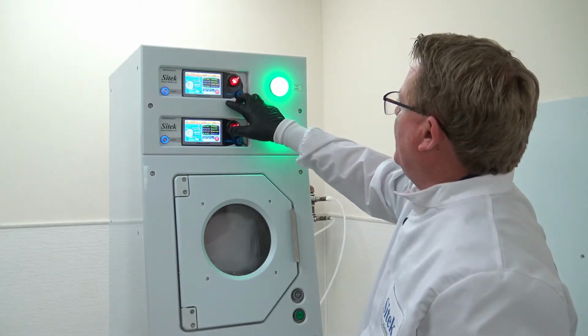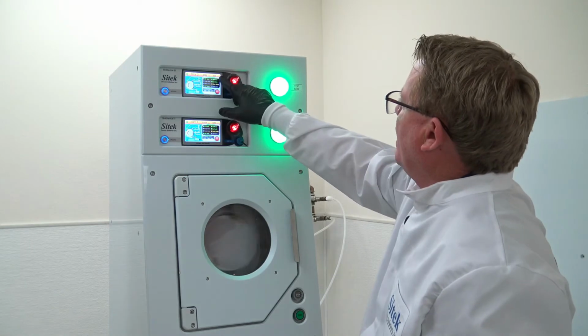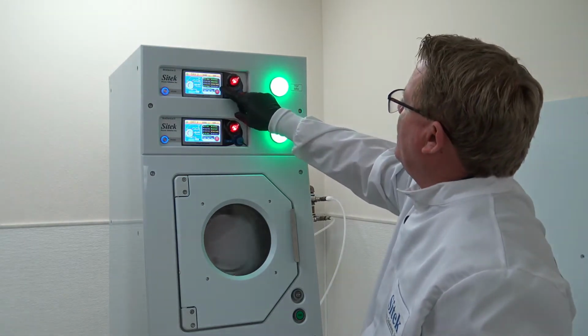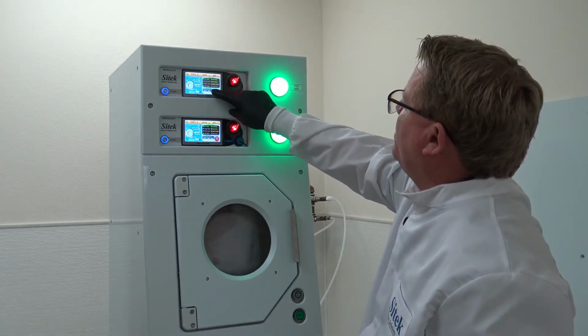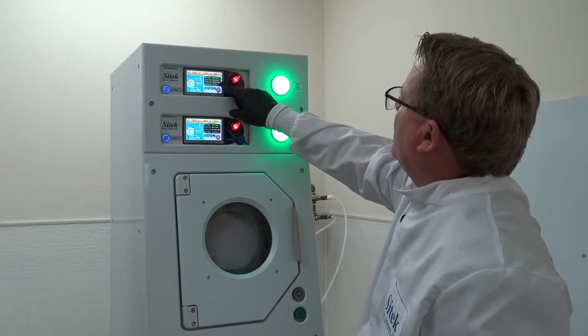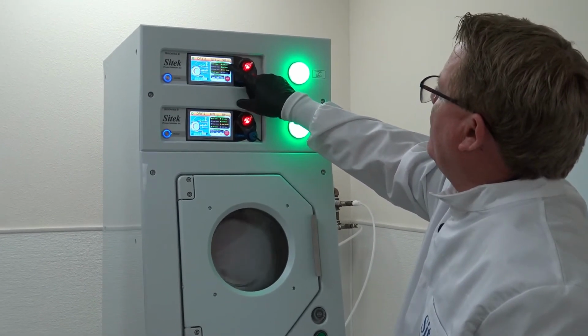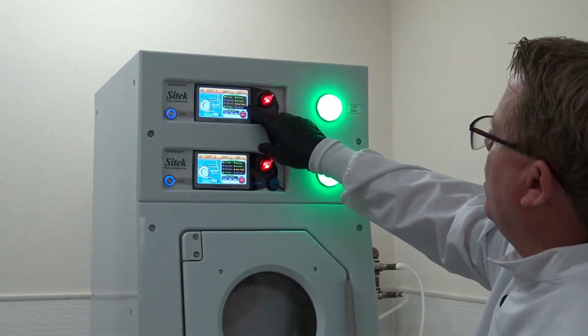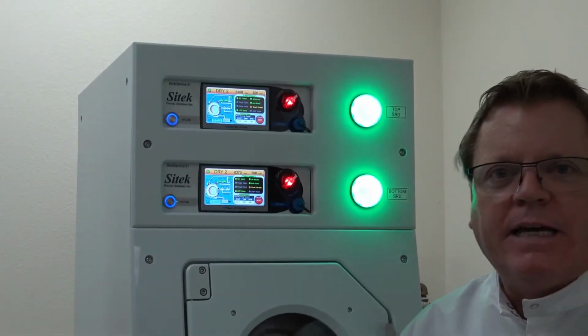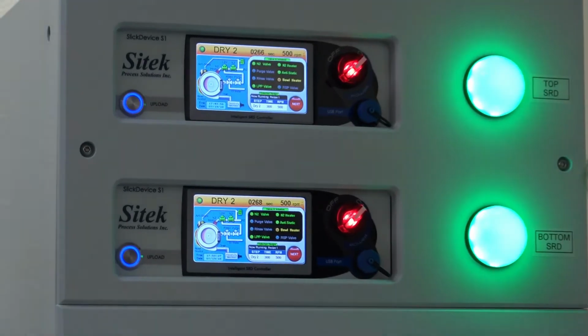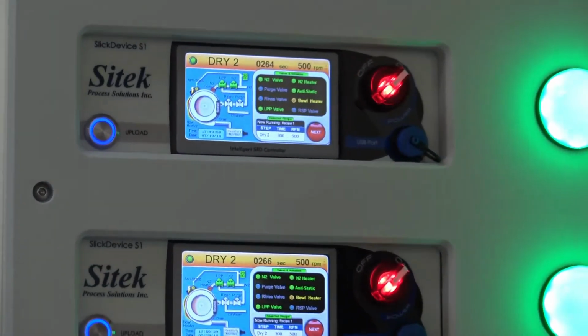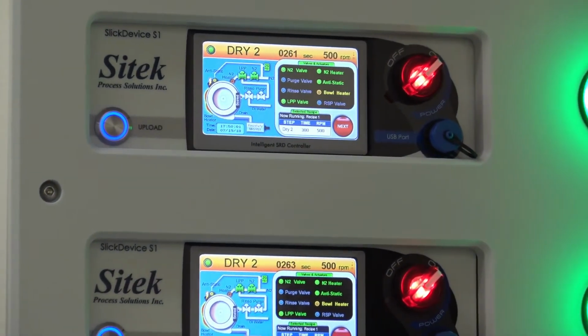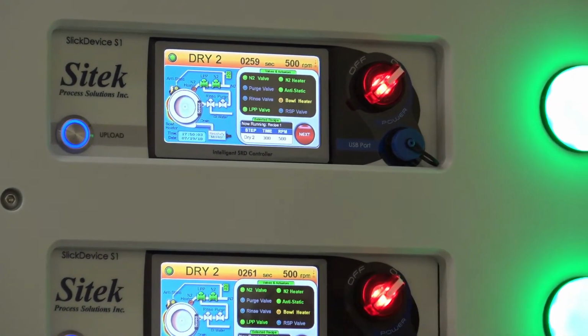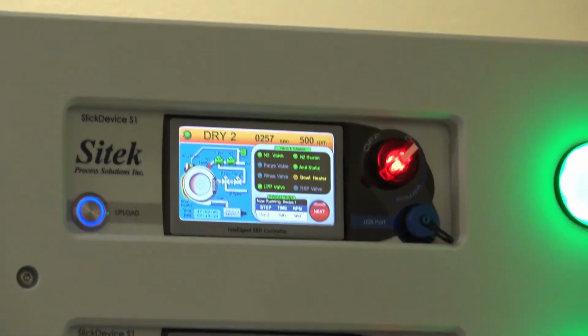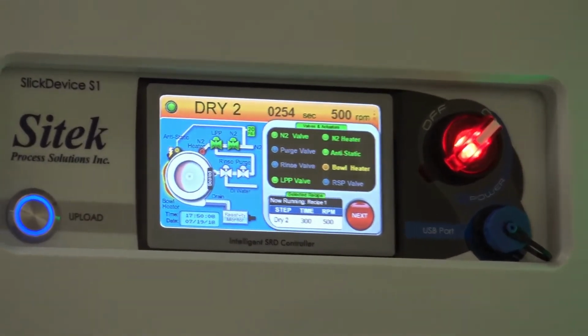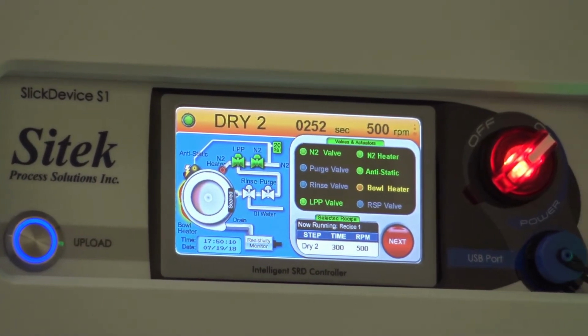Okay, as you see, we're dropping down the RPMs, 500 RPM. Okay, now you can see what's on. The N2 heater's on, the LPP valve, the N2 valve, the N2 heater, the antistatic. The bowl heater is yellow right now. What that means is that we monitor the process switch, and when the process switch closes, which means it wants heat, it turns green. When it gets to temp, it opens up, it turns the yellow amber color, and then when it cools down until it goes under temp, it heats back up again. So you'll see that go on and off a few times.